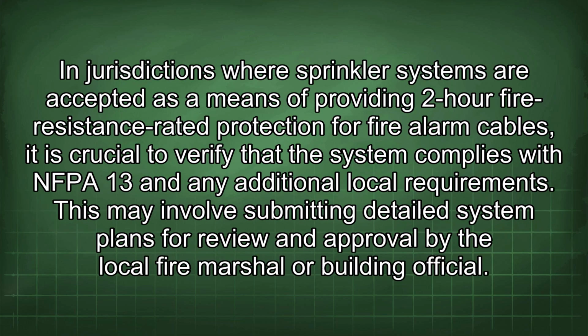In jurisdictions where sprinkler systems are accepted as a means of providing 2-hour fire resistance rated protection for fire alarm cables, it is crucial to verify that the system complies with NFPA 13 and any additional local requirements. This may involve submitting detailed system plans for review and approval by the local fire marshal or building official.